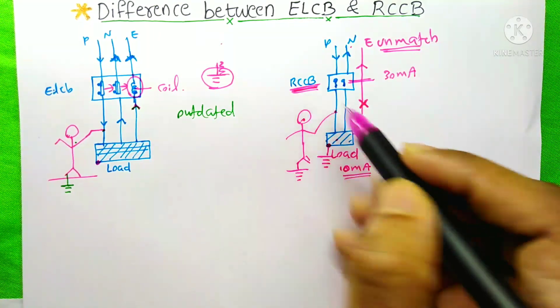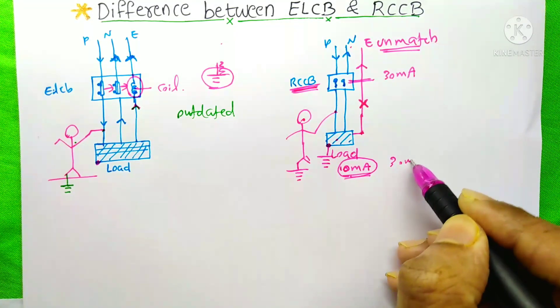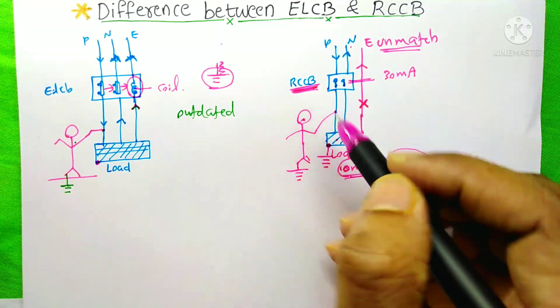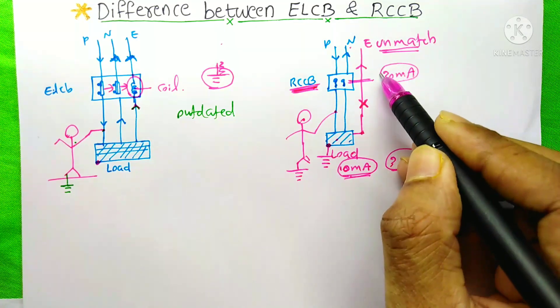At this time, the RCCB will not trip. Instead of this 10 mA, if it is 30 mA or more than this 30 mA, then this RCCB will trip. You know, in our homes, we usually use this 30 mA.